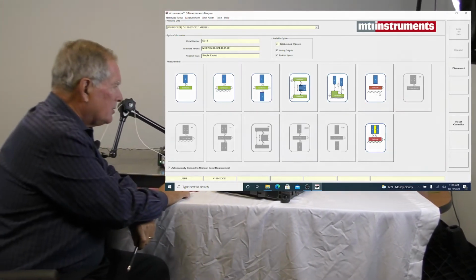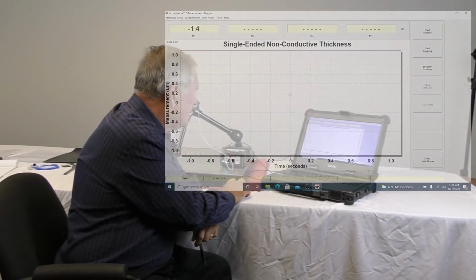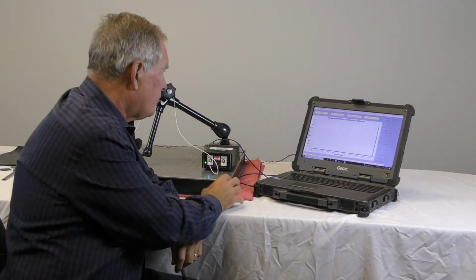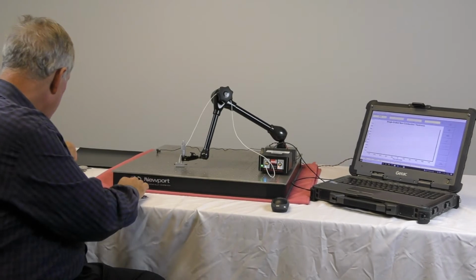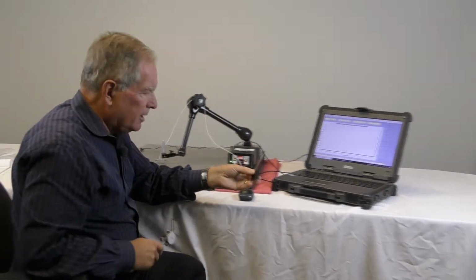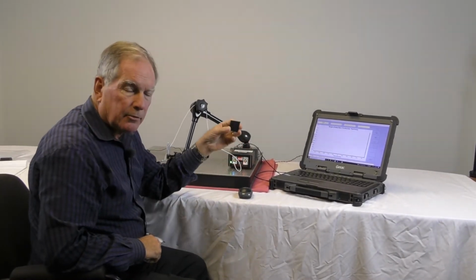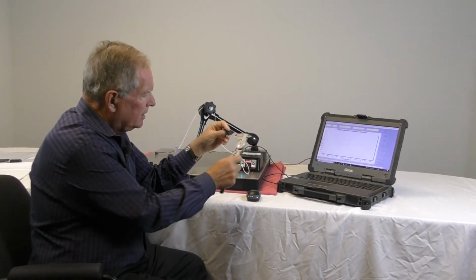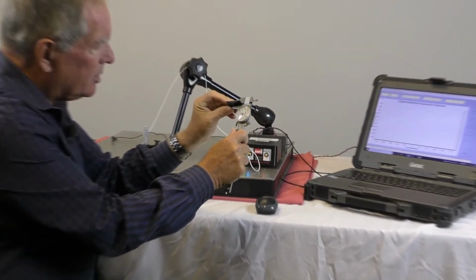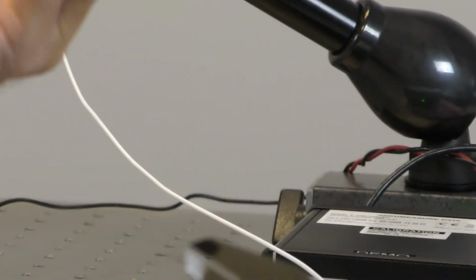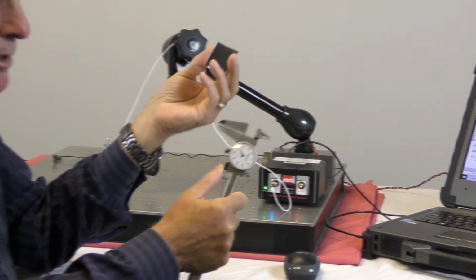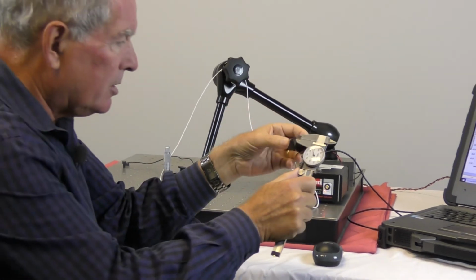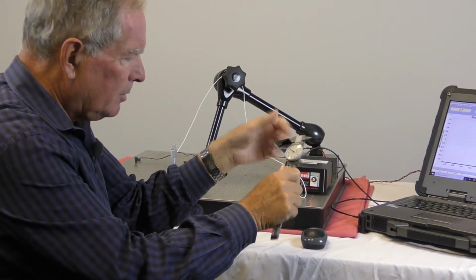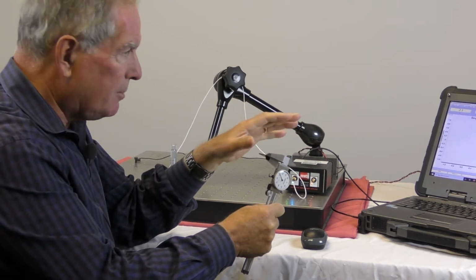So what we would do is click on that, and that brings us over to the measurement screen. Before we do any measurements, we're going to have to calibrate this. So what I've done is I've cut out a sample, or a test coupon, if you will, of this non-conductive material. We're going to use a caliper here to measure the thickness of it. So we either have to know the thickness ahead of time or the dielectric constant. Well, most people don't know the dielectric constants. And we're going to check the thickness of this and then put that in.